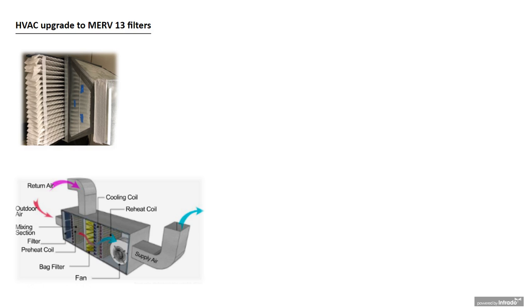So within this ventilation or this air handling unit, that's where you have the filters. You have a filter to filter the outside air, and then you have a filter to filter the return air. If you don't have the proper filter, now MERV 13 filter is what is required by ASHRAE, and that's because it has an efficiency rating of 75% to particles down to 0.3 micron. If you have less than that, basically those pathogens are going to fly right through this filter and then be released into the supply air. That's why the upgrade to the filter is critical and part of the recommendation for CDC and ASHRAE.